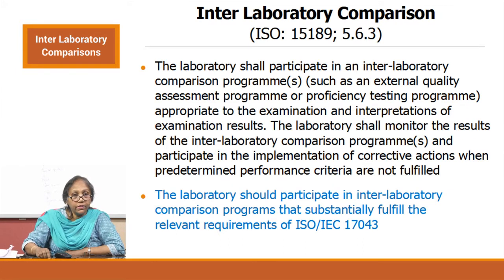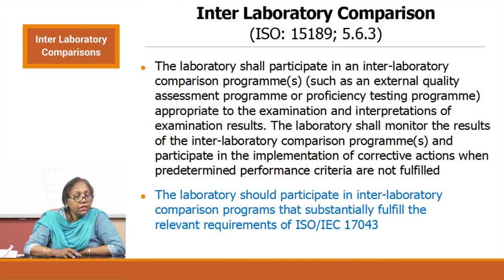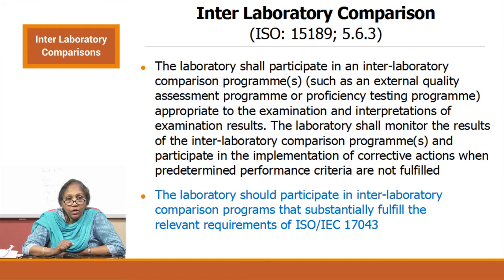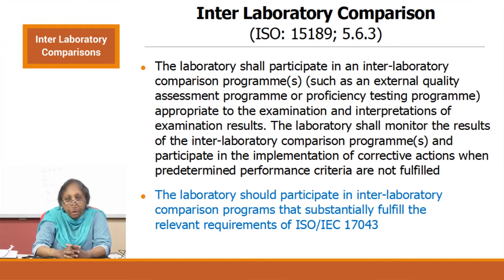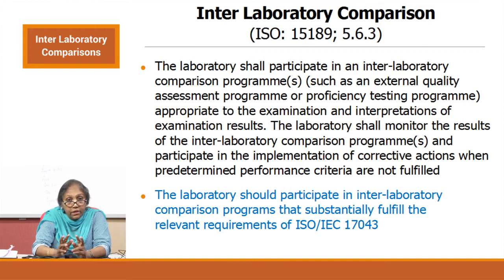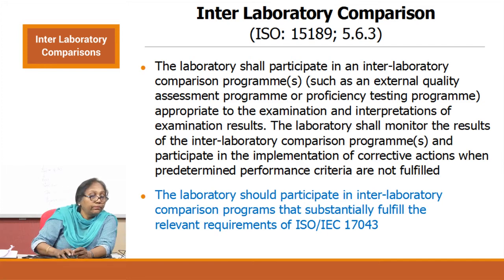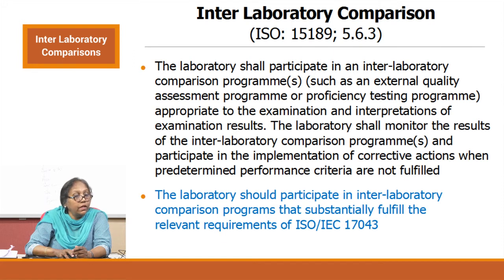Let us start with 5.6.3 interlaboratory comparisons. We already talked about peer group comparisons in an earlier video. We will go into the details of other registered mechanisms. I would like to caution you that peer group, though extremely useful, is not considered a valid EQAS participation at this point. You may have your peer group, but it is not considered a valid interlaboratory comparison under proficiency testing or external quality assurance. If there are registered EQAS programs, you have to register in those.